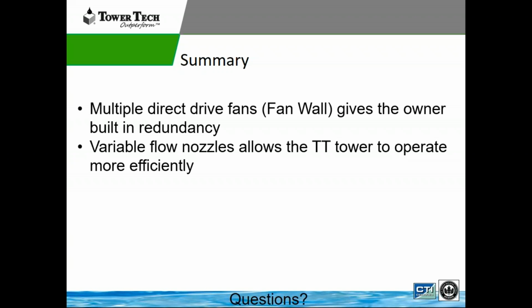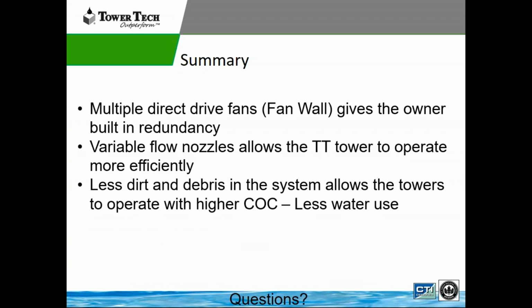Variable flow nozzles allow the tower tech machine to operate more efficiently. As we said, at part load, we're running one chiller. We're running half the flow through the full fill. We're able to reduce the fan speed. We can operate down to 6 hertz on a direct drive fan, so we can operate very efficiently at that point.